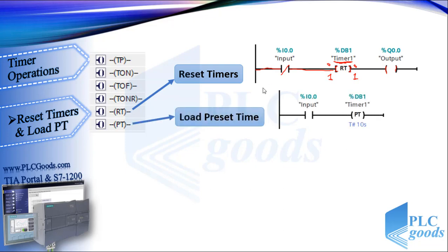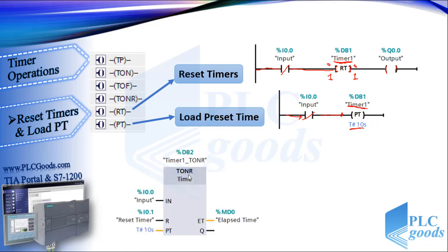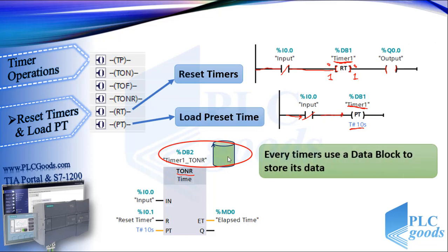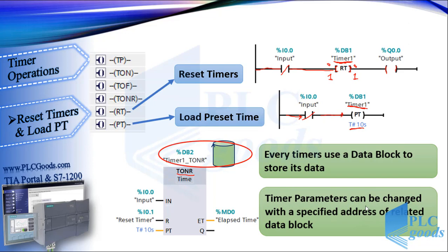With the second instruction, we can change the preset time of timers. Every timer uses a data block which is used to store its data, such as its preset time. So timer parameters can be changed with a specified address of the related data block. Let's see the three last instructions in TIA software — the others are similar.